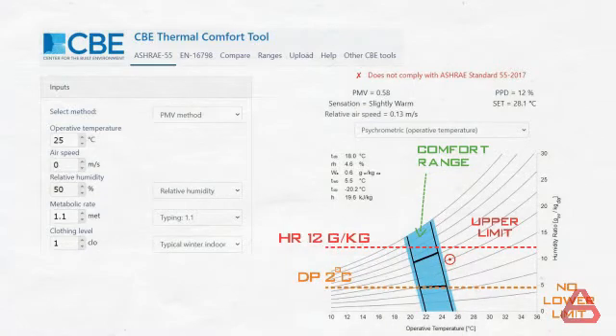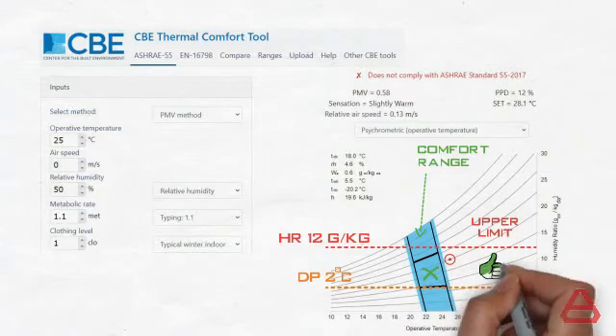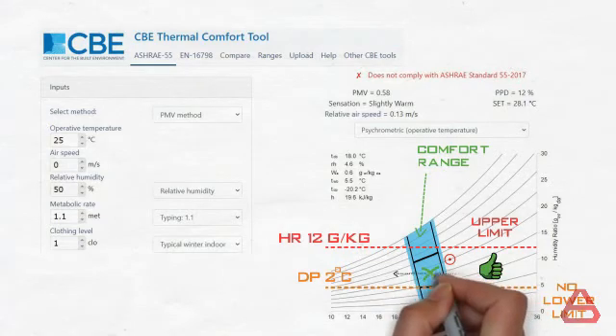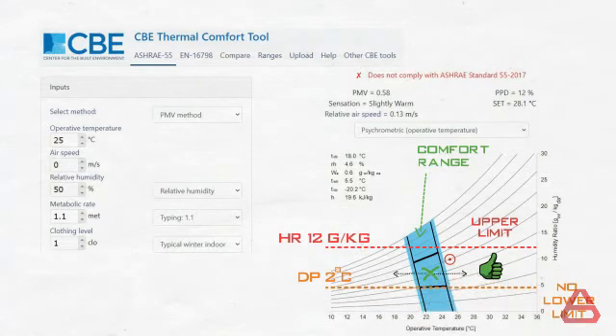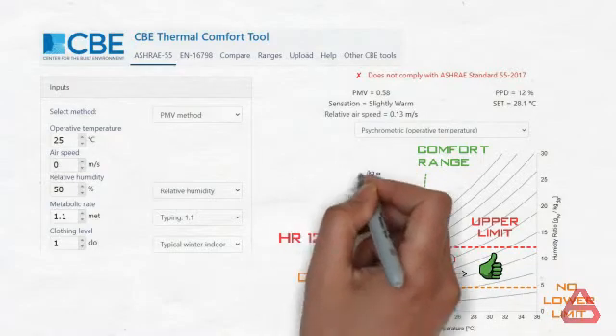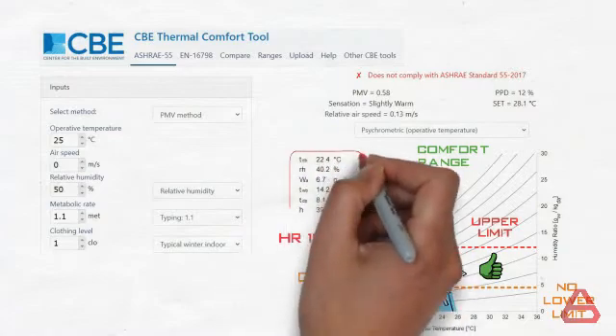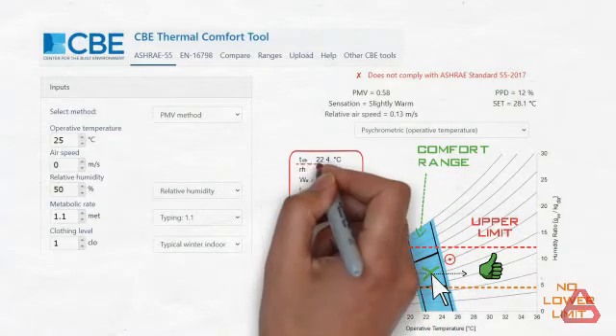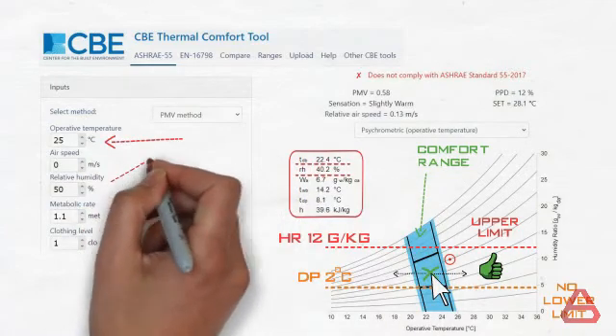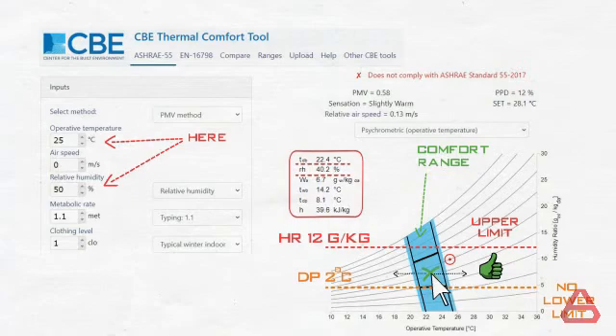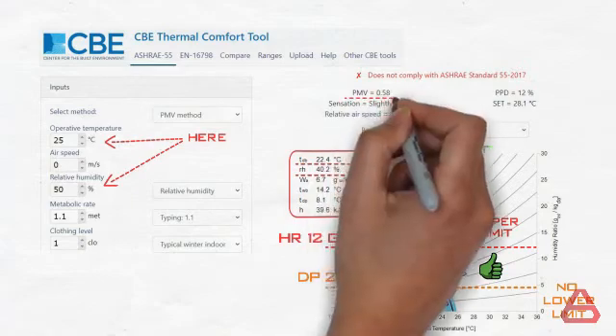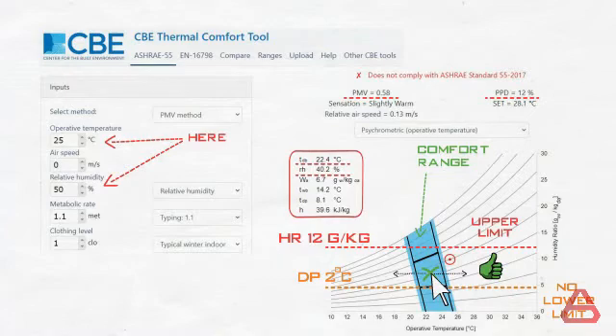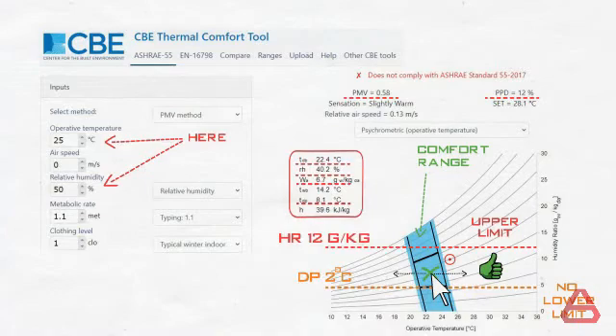What you can do is select the point in the center of the comfort zone, since they generally produce good results and have a wider flexibility margin in both directions. Hover over the center with the mouse and in real time the tool will return all the air properties. Check the returned humidity and temperature values and then input them back in the input section to get the resultant PMV and PPD. You can also check the dew point temperature and the humidity ratio at this point to avoid crossing over the recommendations.